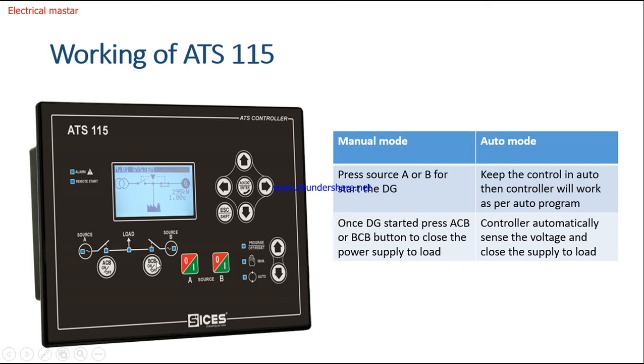Similarly, when main supply comes back and you want to remove the generator, you just press this BCB button again, so the breaker will open, and the generator will keep running. You just press the source B button and the generator will be off. Then for source A, there is no need to press the source button because it is a transformer. You just check whether the voltage is available or not. If the voltage is available, just directly press the ACB button. So the ACB will be closed and the supply will connect to the load. This is the manual mode.